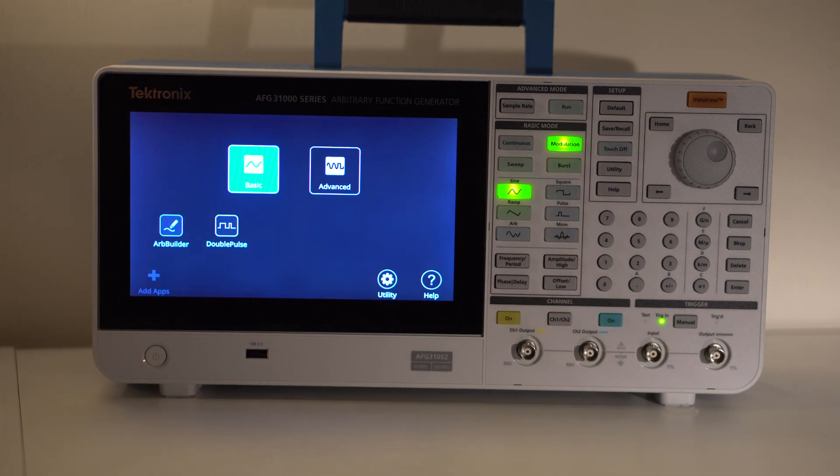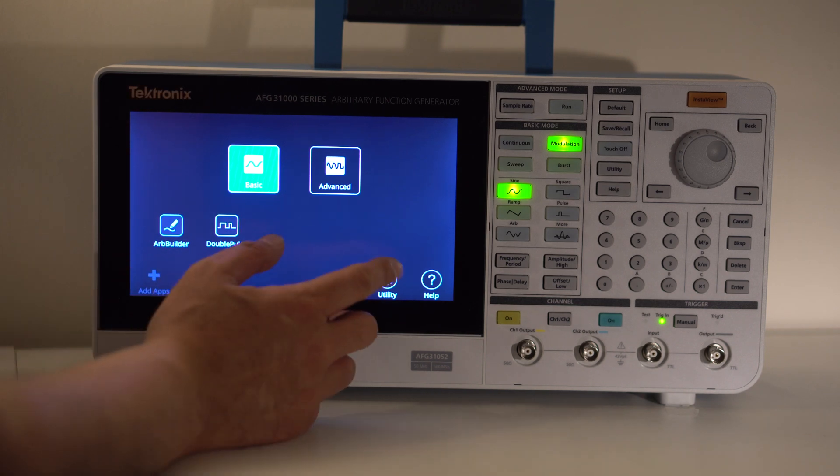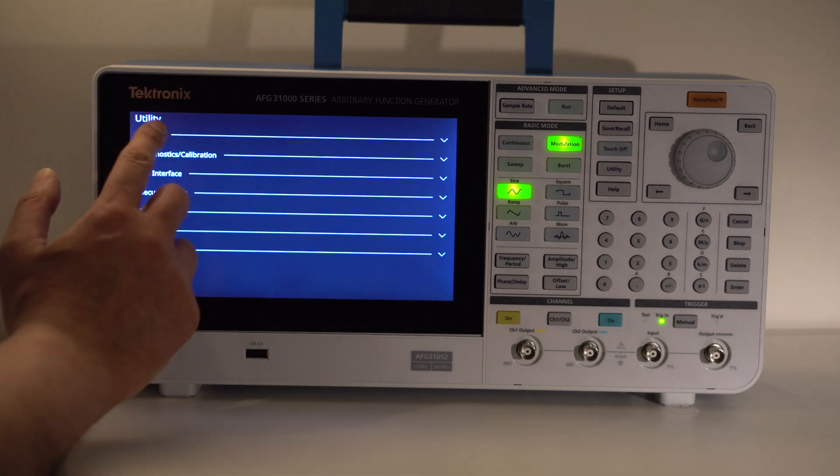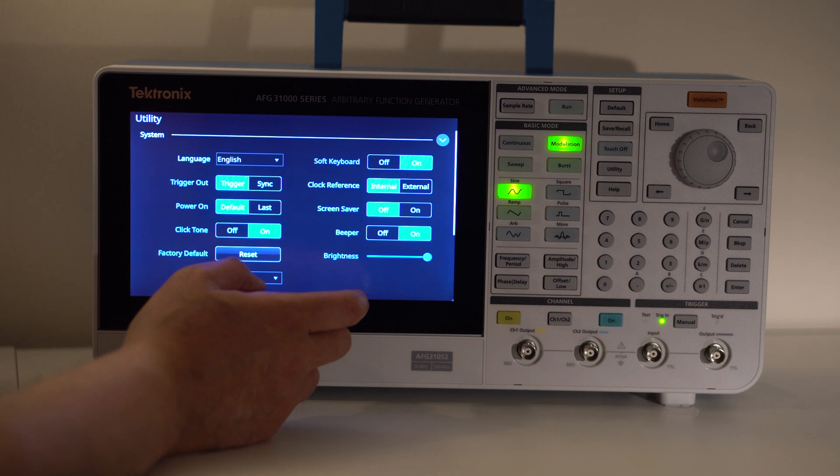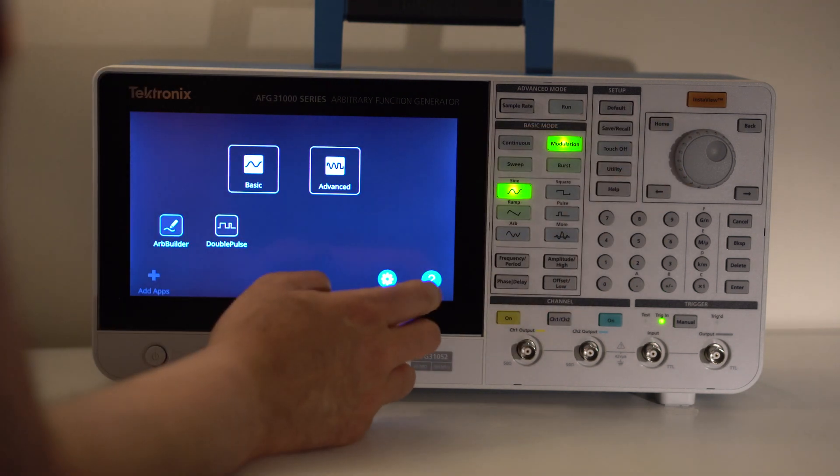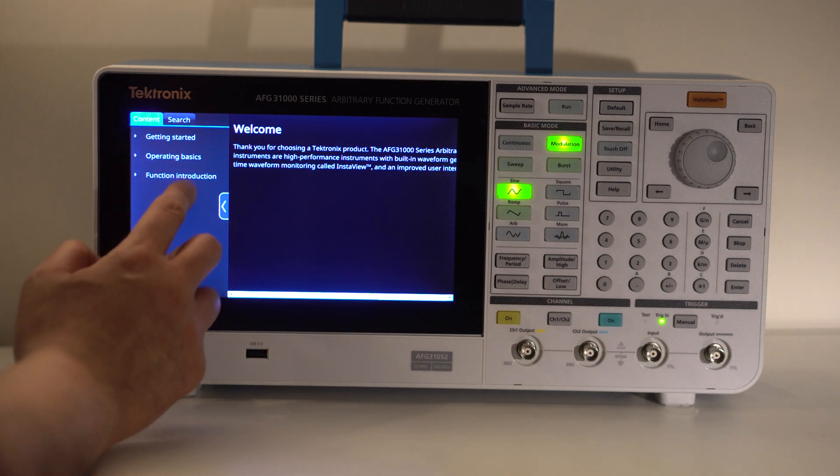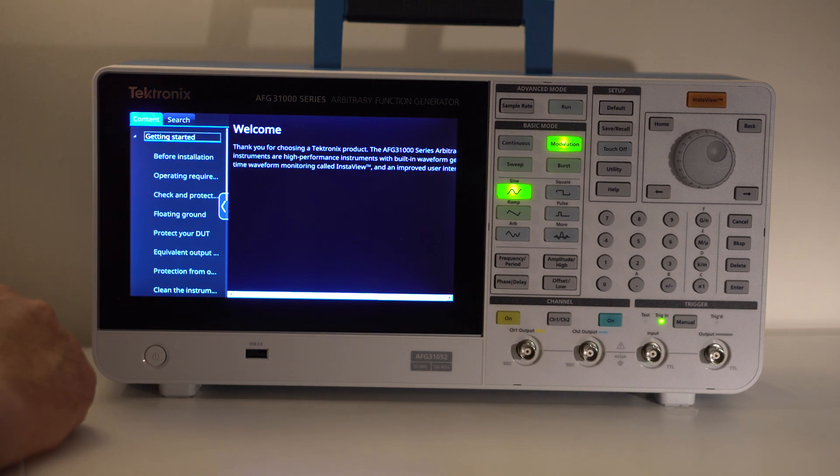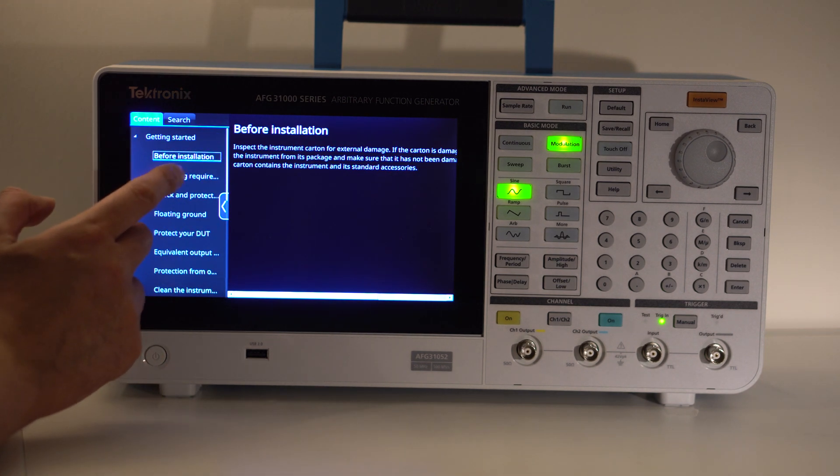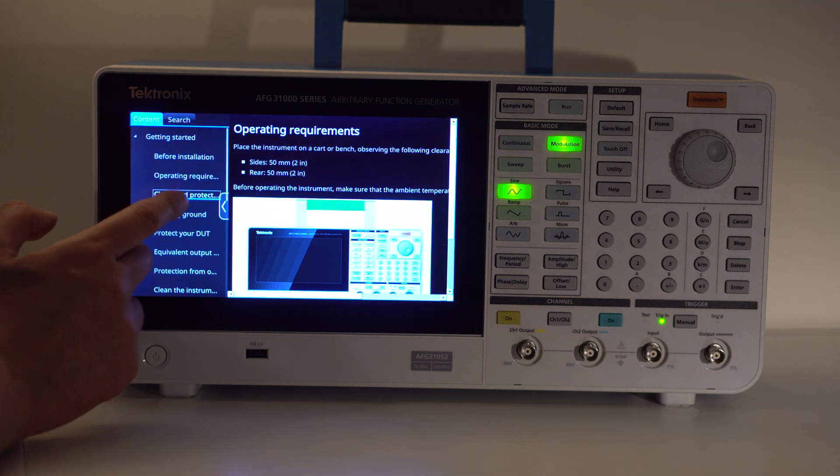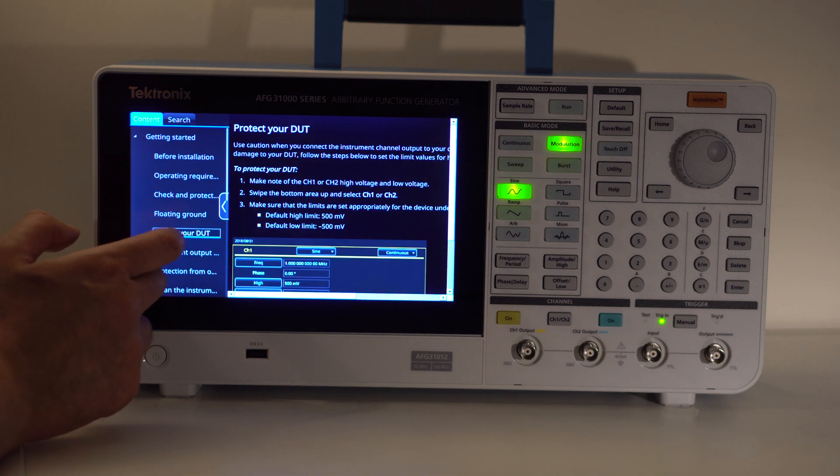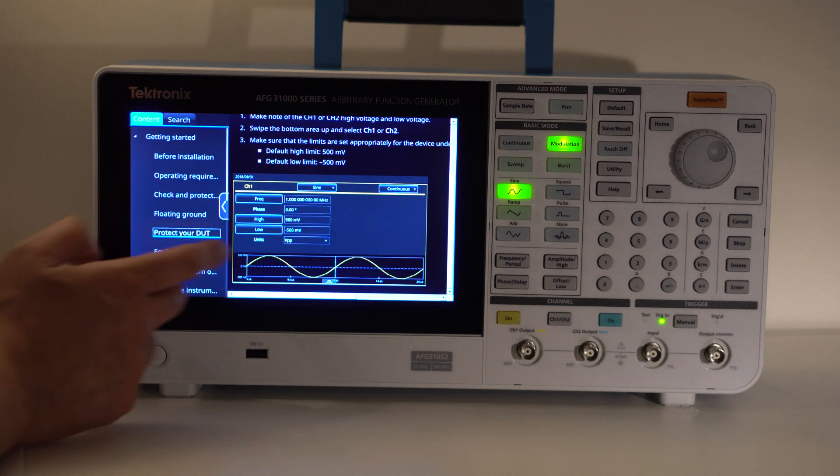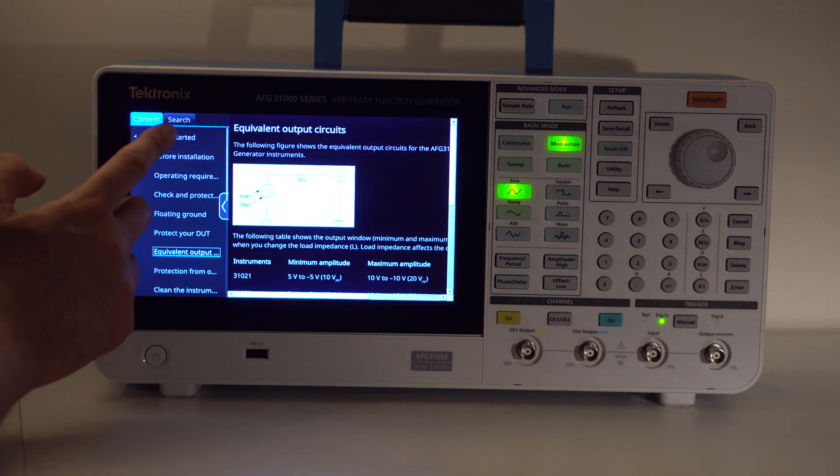It's a very modern instrument with a great user workflow system where you can select either a basic traditional mode or a more advanced sample-based mode. Virtually all of the configuration is on a single screen with virtually no embedded or hidden menus, which makes it easier to use and reduces misconfiguration compared to older instruments. Everything is software-upgradable, apart from the number of channels.